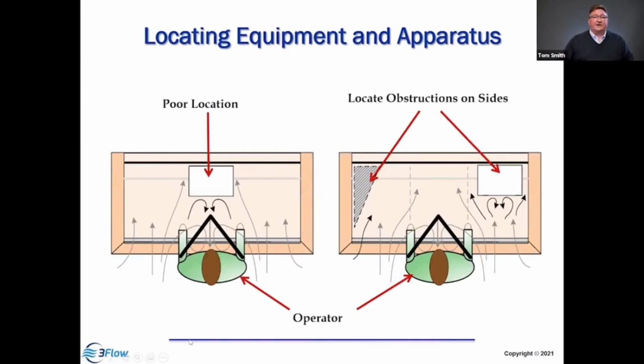All right, I won't make you watch that again. All right, so now you can also affect airflow patterns based on location of obstructions. If they're directly downstream of the body, they're going to create more impact on containment than if they're on the sides. We want to have the space between the body and the slot open to the degree of potential, and that's why we generate downstream of the body during tracer tests.